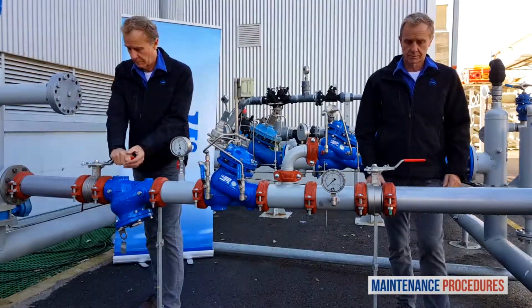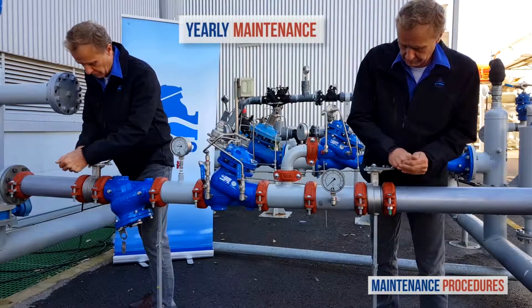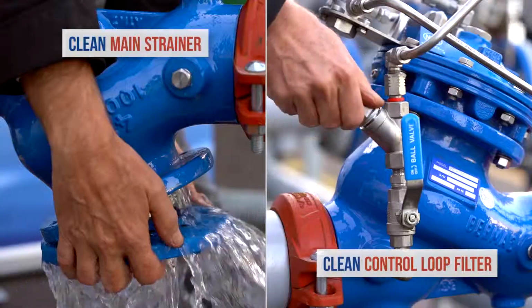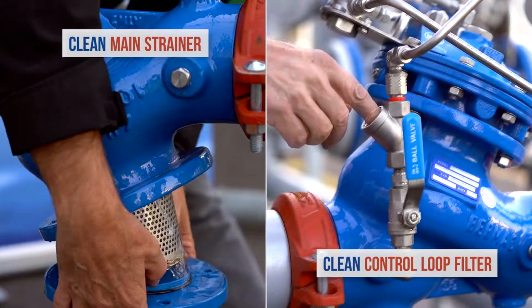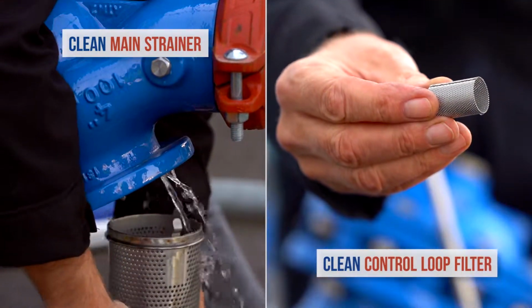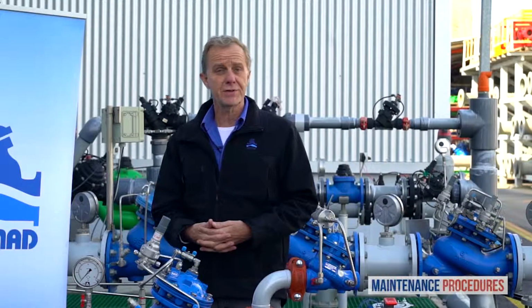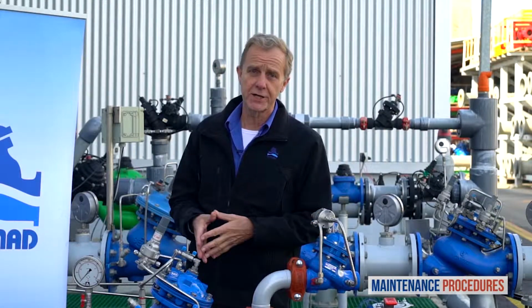be. Once a year, close both the upstream and downstream isolation valves and clean the main strainer and the valve control loop filter. Every 3 to 5 years, inspect the internal conditions of the pressure reducing valve.